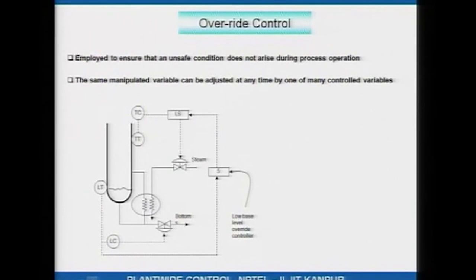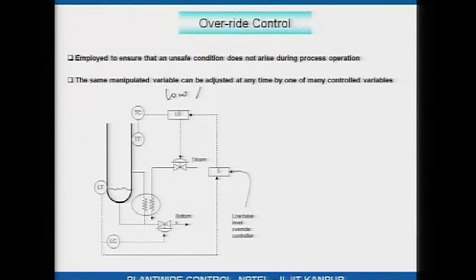Here is a simple example — the bottom of the stripping section of a distillation column. You have the reboiler which is taking in steam, and this steam is causing vapour to boil up. Ordinarily, the steam valve is moved by the temperature controller. The LS here is actually a low select — it takes in the signal output of the temperature controller as well as another signal I will explain shortly.